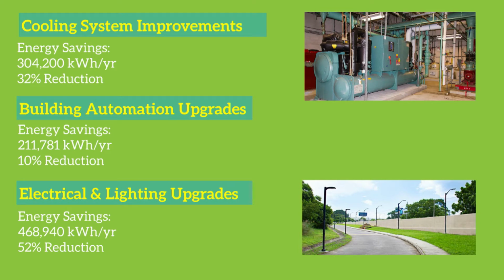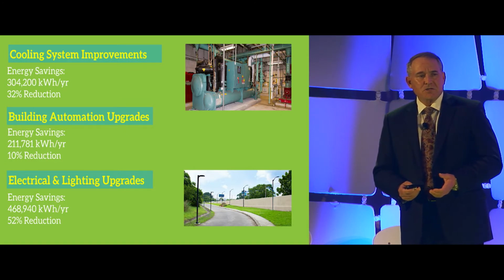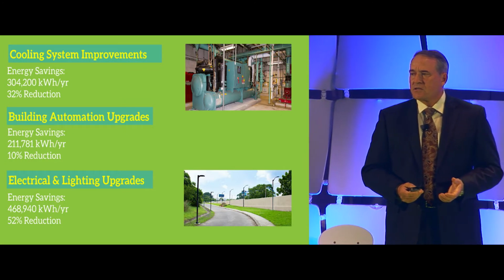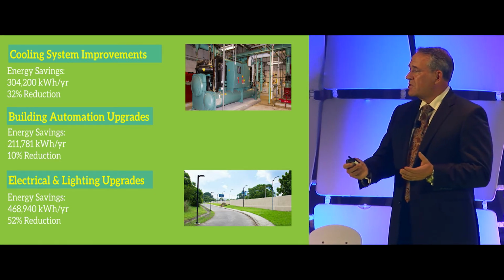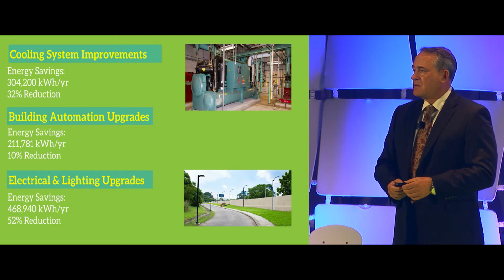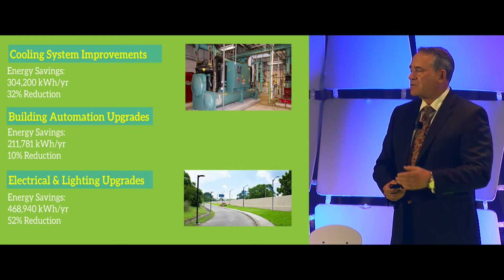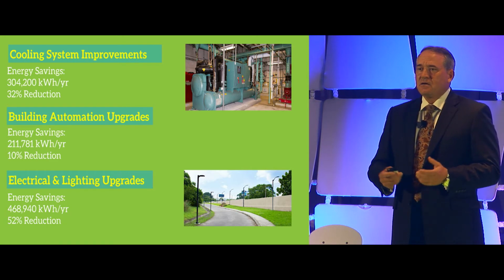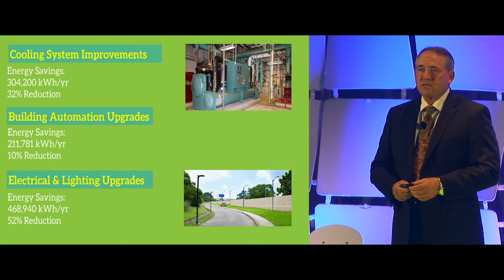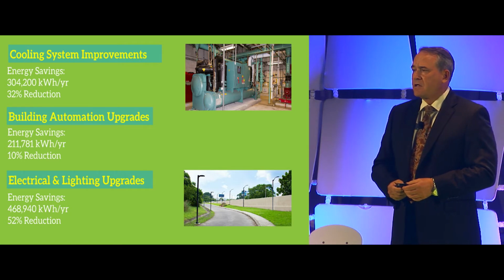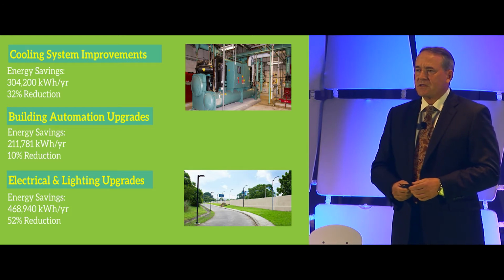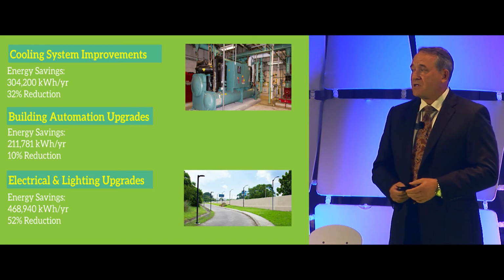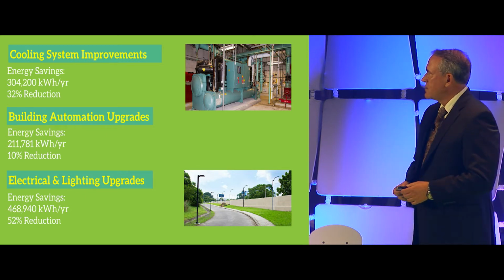Quickly hitting the chiller: what we found was they had two 325-ton chillers in place serving the load capacity of the compound, but their night load and weekend load was only about 150 tons, so they were trying to throttle down those chillers - very inefficient. We put in a brand new 210-ton water-cooled screw chiller that now handles the weekend and night loads, and also operates about 20% of the daytime operational load. It's paying for itself in less than 10 years, replacing 6-year-old chillers from the original design.